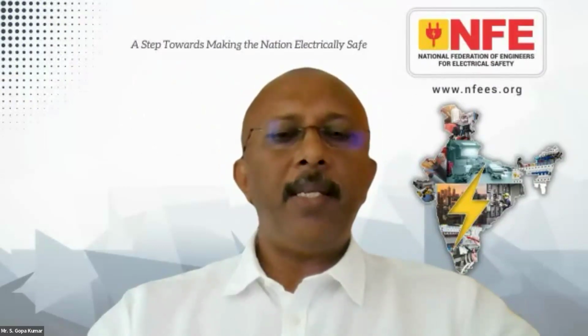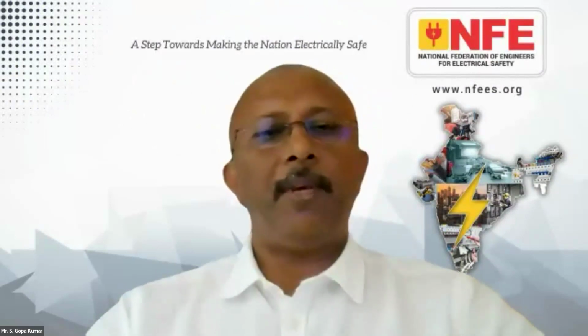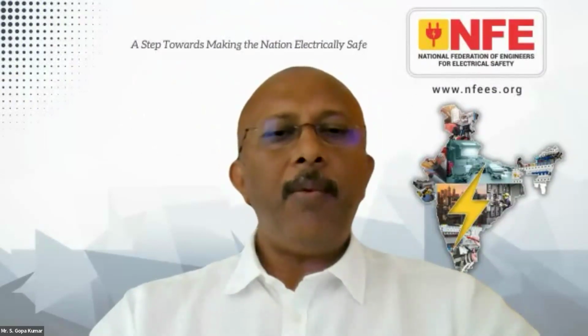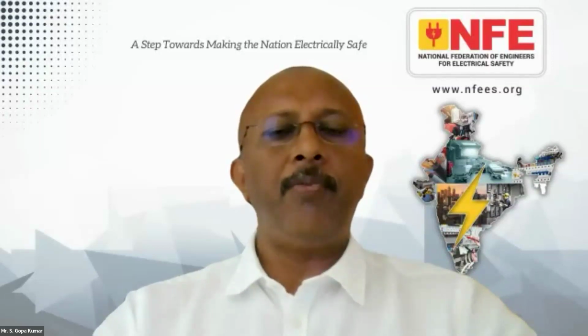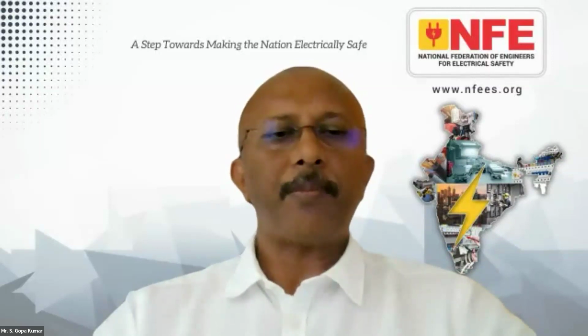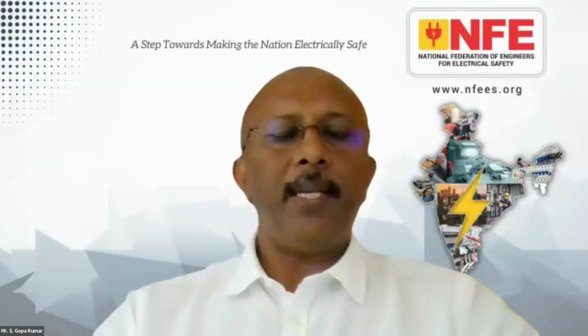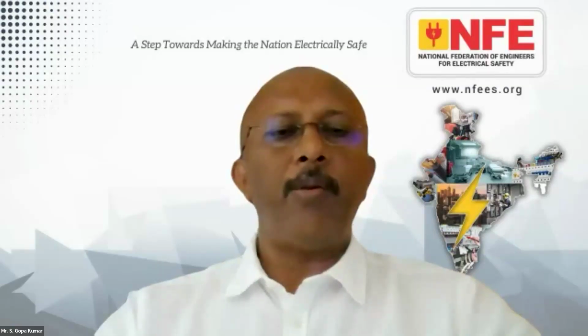So we have to make the installation, and we have to maintain the installation, in such a way that we just forget about ignition due to electricity from the entire area. In technical terms, we say thermal effect. Electricity, when you use it for normal purposes, should not create a temperature rise more than certain limits. As a result, arcing and spark over are avoided. Now, in an existing installation which is already installed, the wires are running somewhere, and actually nobody knows.